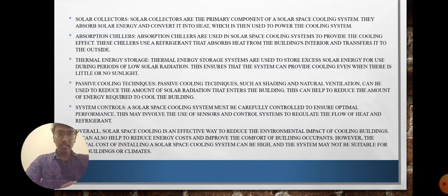Solar collectors are one of the equipment. Solar collectors are the primary component of a solar space cooling system. They absorb solar energy and convert it into heat, which is then used to power the cooling system. Absorption chillers. Absorption chillers are used in solar space cooling systems to provide the cooling effect. These chillers use a refrigerant that absorbs heat from the building's interior and transfers it to the outside.